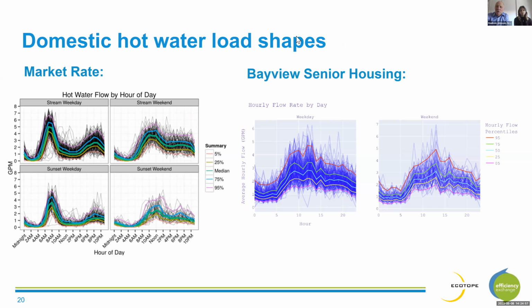One thing that made that a little bit more challenging is that the load shape of the hot water usage at Bayview senior housing is not the same as a typical worker housing building, which is that shown on the left there with the big morning peak and a secondary evening peak. The senior housing, since nobody's going anywhere, people get up at different times and they use their water more. There's more water use in the middle of the day. This makes it easier to shift usage out of that morning peak time, but makes it harder to shift out of the second evening peak because it's harder to catch up with your storage.